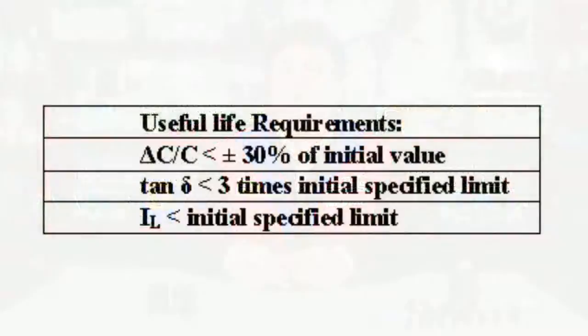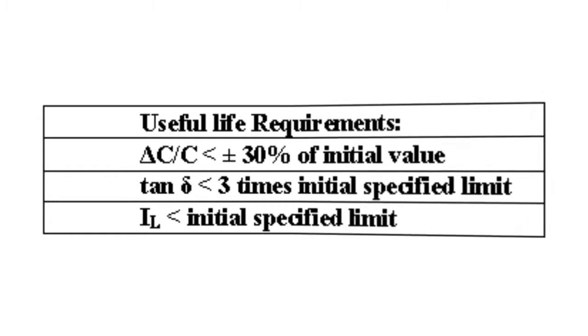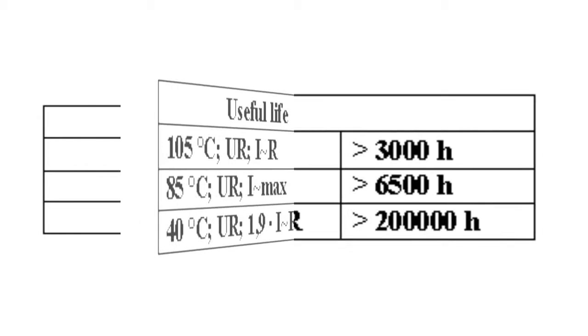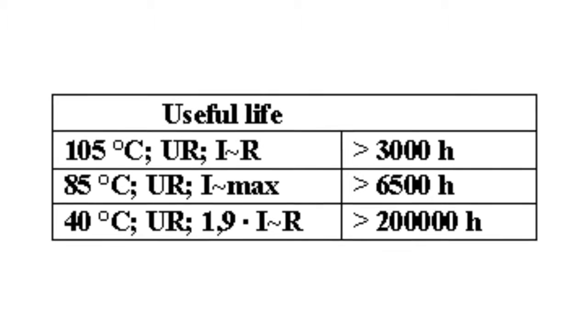Capacity is decreased by more than 30%. The loss tangent is increased more than three times. The leakage current exceeds the limit stated by the manufacturer. The useful life is normally indicated for several temperatures.